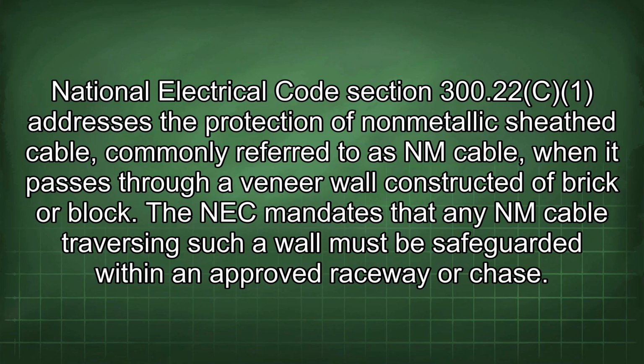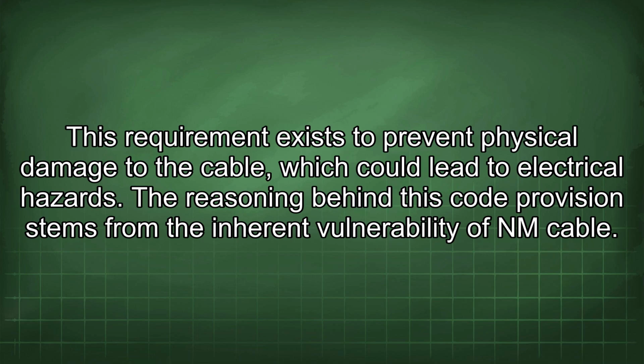National Electrical Code Section 300.22 addresses the protection of non-metallic sheathed cable, commonly referred to as NM cable, when it passes through a veneer wall constructed of brick or block. The NEC mandates that any NM cable traversing such a wall must be safeguarded within an approved raceway or chase. This requirement exists to prevent physical damage to the cable, which could lead to electrical hazards.